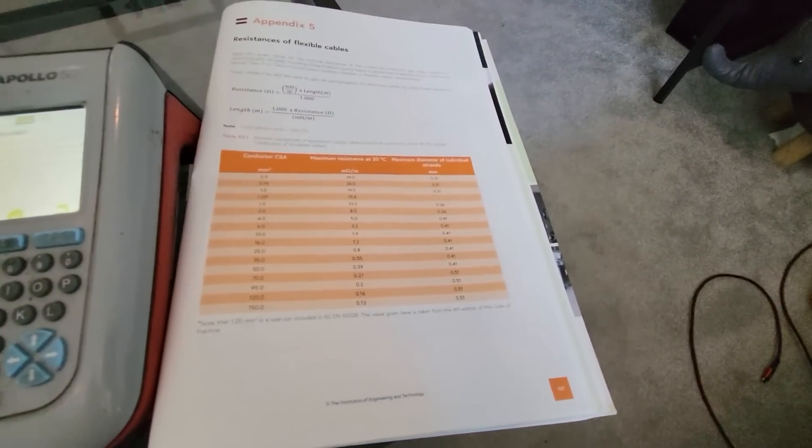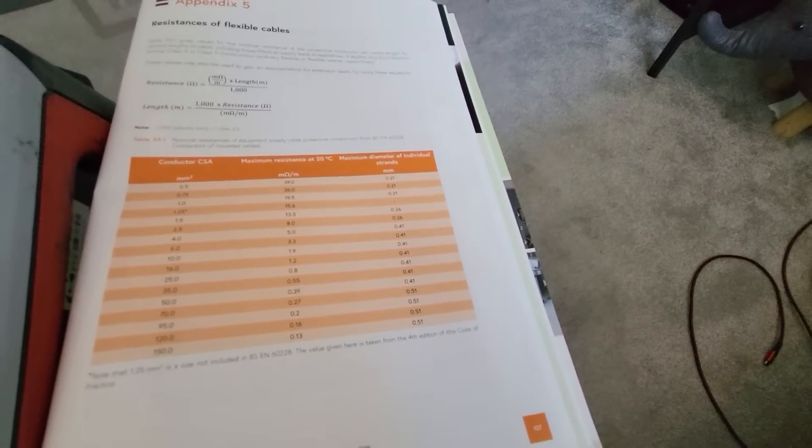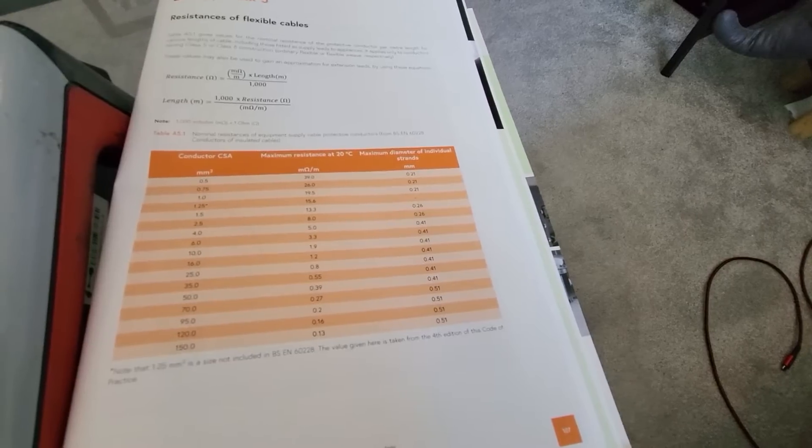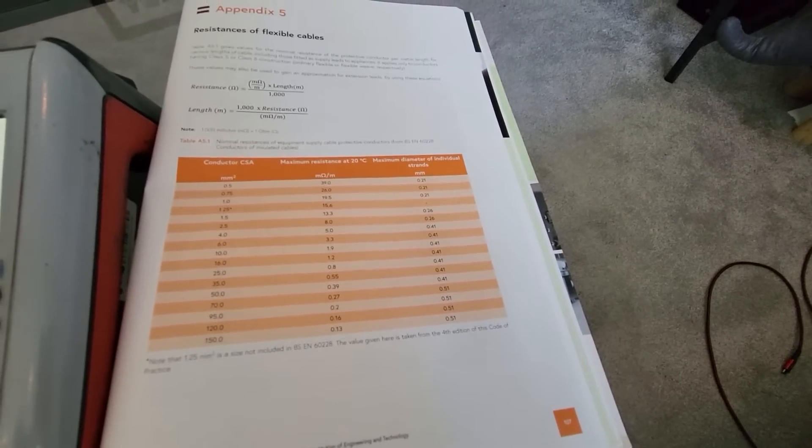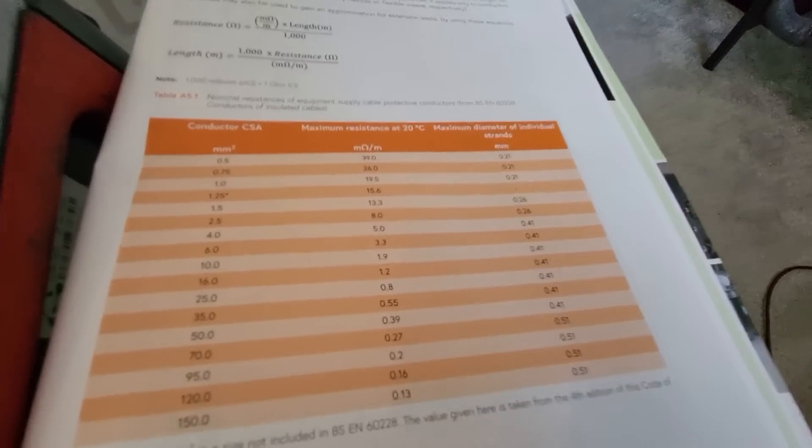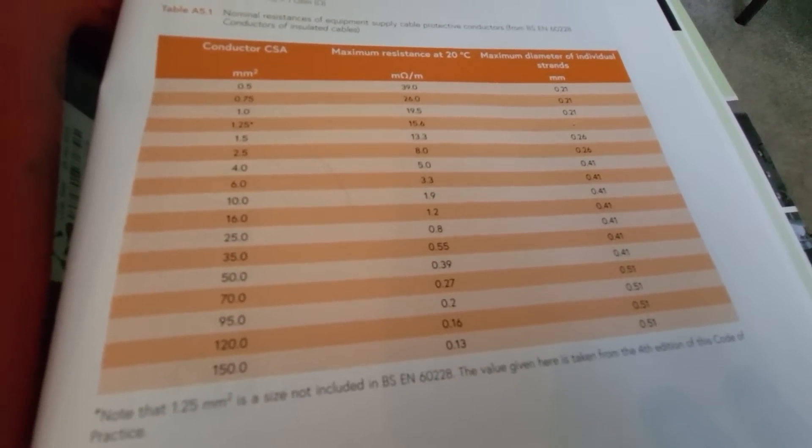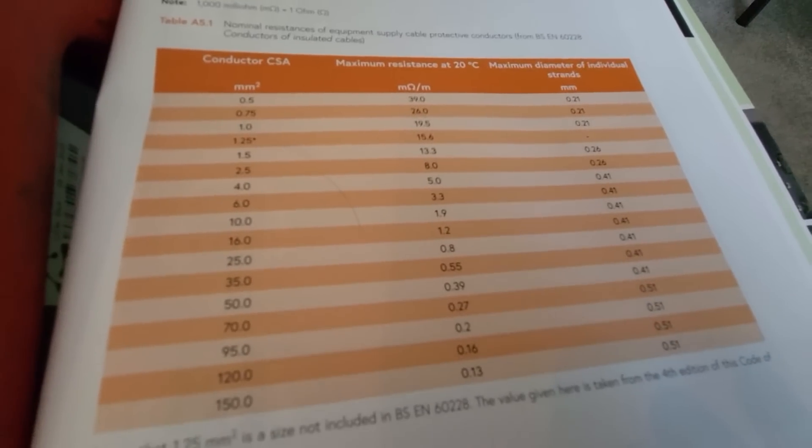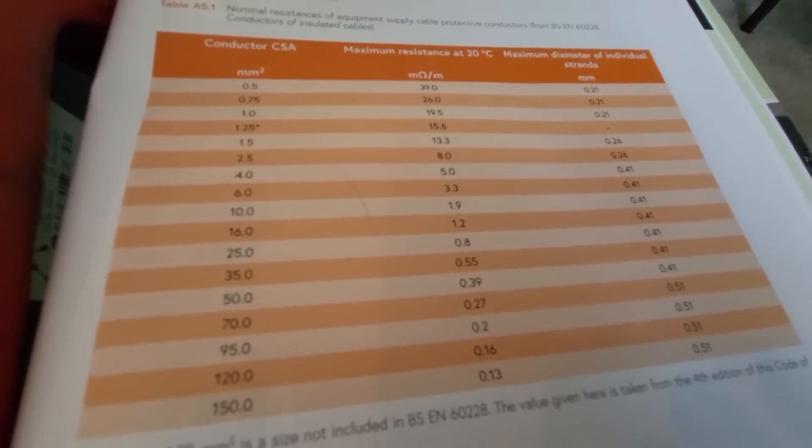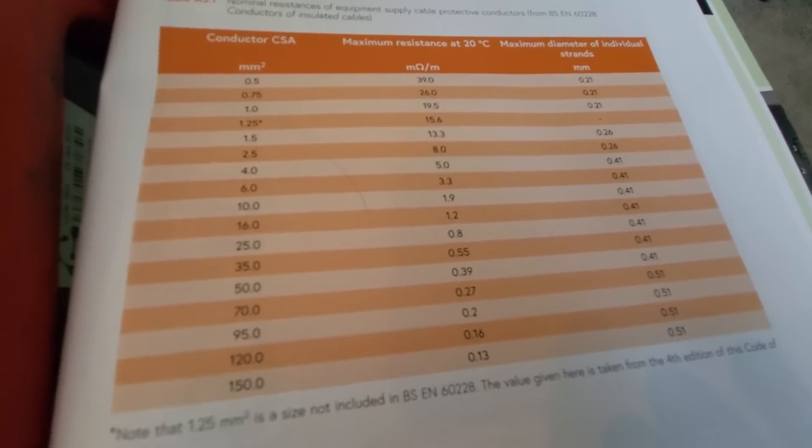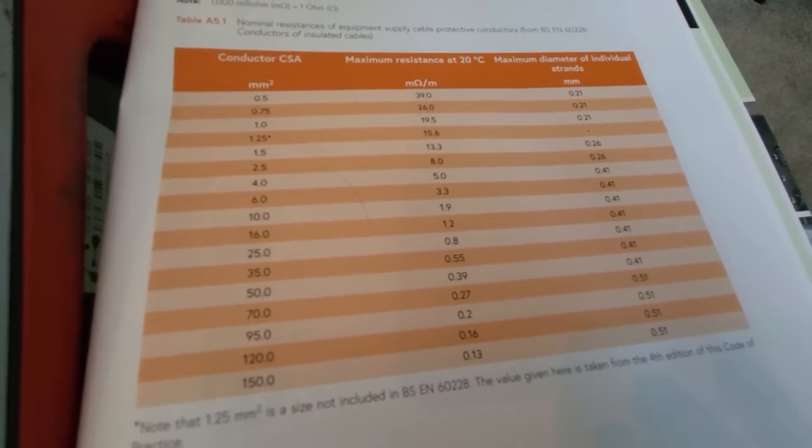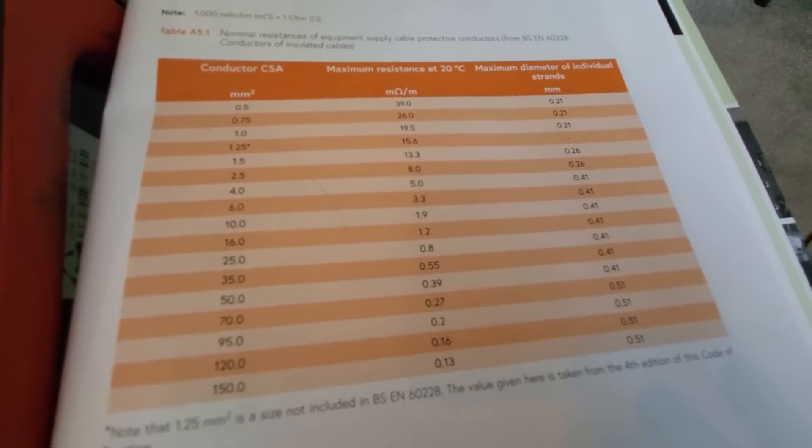So one way of doing that is if you have a copy of the Code of Practice like I do here, and you will see here that this gives you resistances of various cables at 1 metre lengths. So if you can see here the conductor CSA, which is cross-section of cable. Now, I'm going to hazard a guess here that the majority of cables you will come across will be between 0.5 at the top and probably 4 mil halfway down the table there.